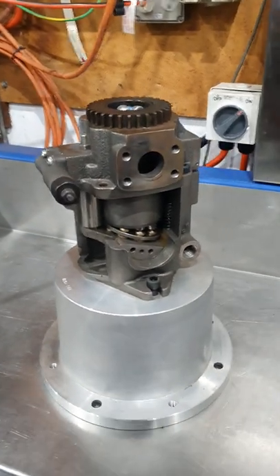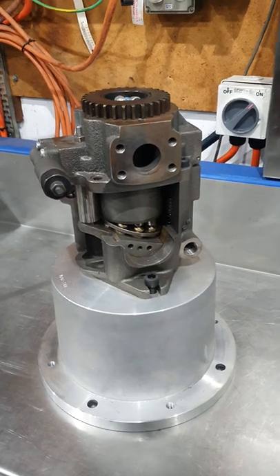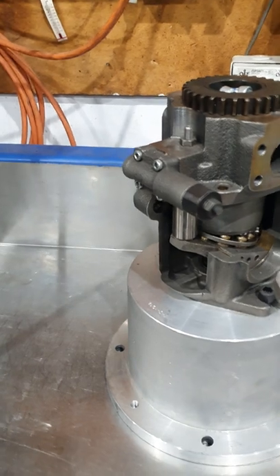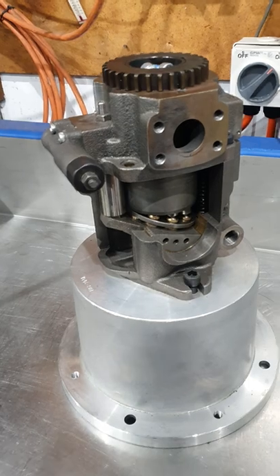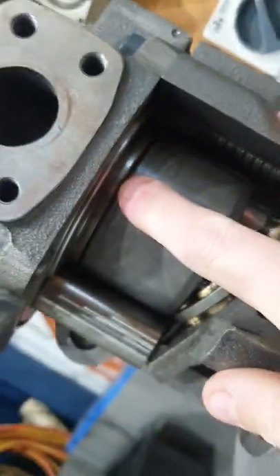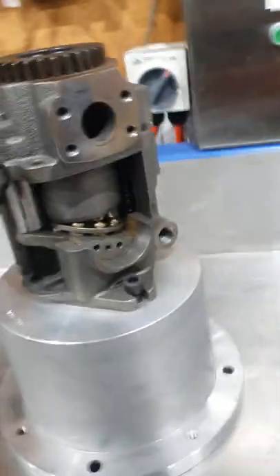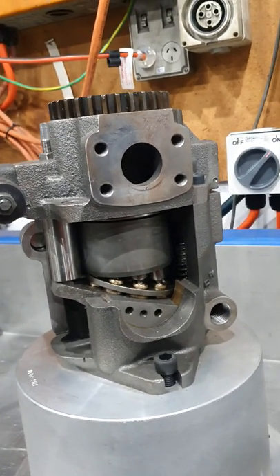I thought I might give you a rundown on what the three most common failures are with a piston pump. First and easiest — just pure contamination. In here you've got a valve plate where the barrel runs on, and that's got to form a seal to basically keep the pressure in there, keep the oil in that you're pumping.